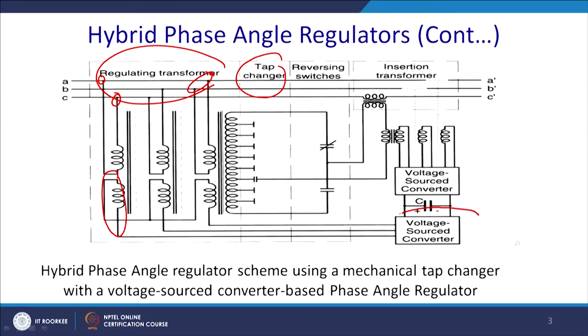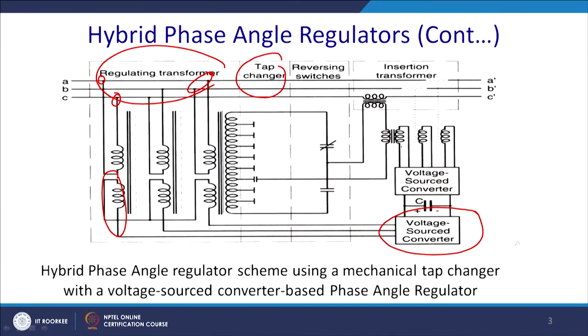Instead of applying in quadrature and phase, this has a property that if it is a phase vector, it can inject in the phase steps of the two level inverter of 60 degree. So you can make the combination of the voltage, let us say 65 degree you require to inject, that can come from the quadrature as well as by this. So these two voltages will be added in series and will give you the desired voltage. And this converter acts very fast, for this reason the compensation will be very accurate.